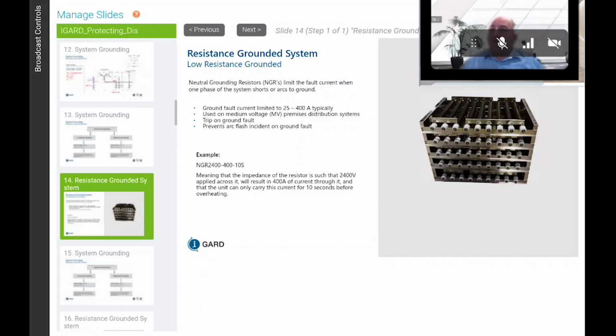One common question that we get is, so we get questions all the time from people who say they need a low resistance grounded system and they want to limit the fault current, but they don't know what value. What determines the value in a low resistance grounded system is not the resistor, is not the distribution system, it's the protection system.